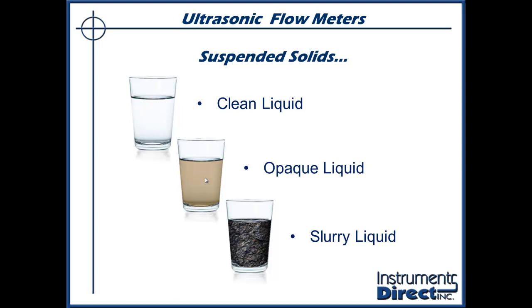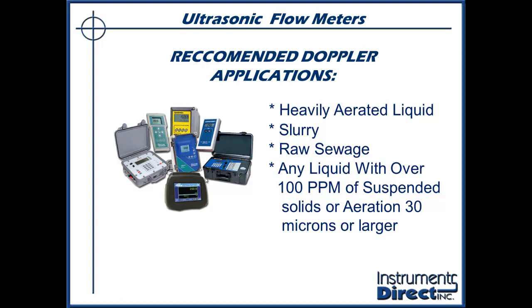Applications with chunks of stuff — slurry applications that look like oatmeal, sludge, mining, paper stock — those have high levels of solids and are applications where you don't want to put an invasive device in the process stream because it will clog, fail, or coat. Perfect applications for ultrasonic Doppler flow meters. Generically, ultrasonic Doppler flow meters work in sewage, definitely sludge, wastewater, mining, dredging, pulp and paper, and slurry-like applications. You need 100 parts per million suspended solids or aeration, 30 microns or larger, just to get it to work.